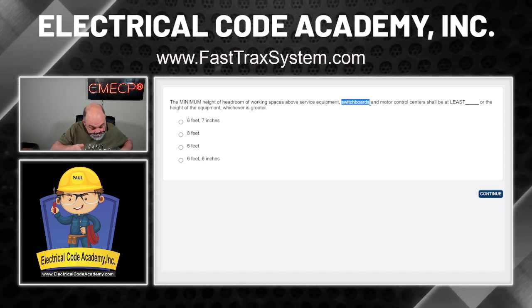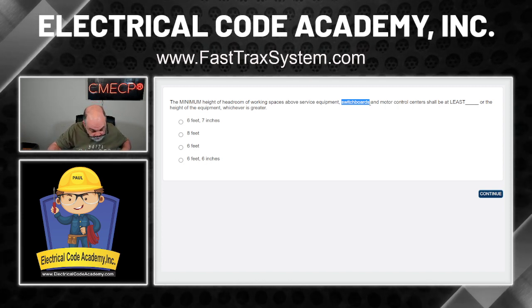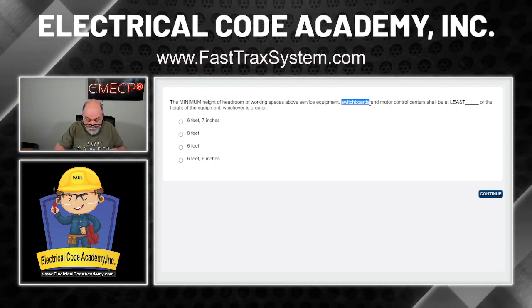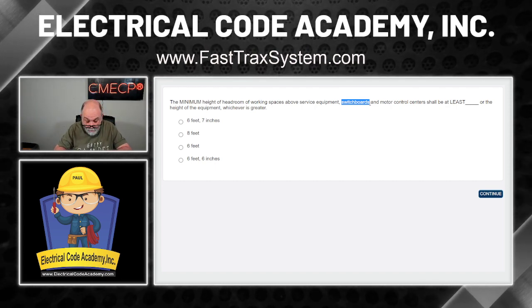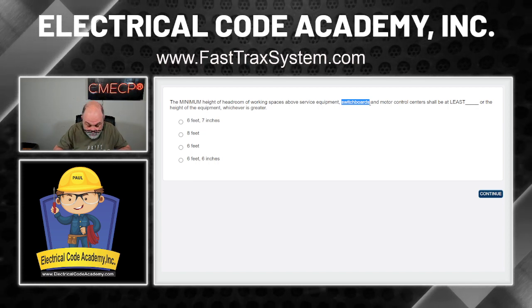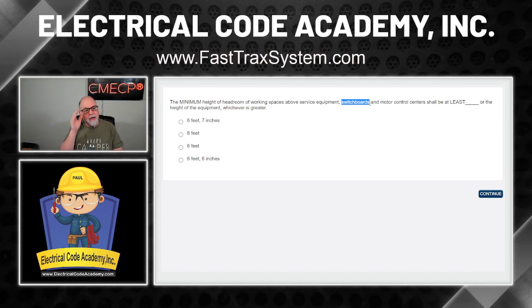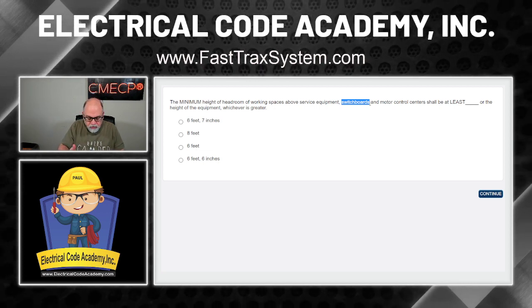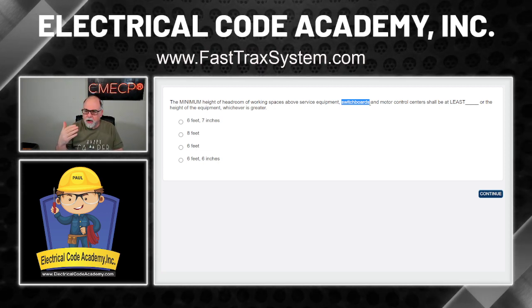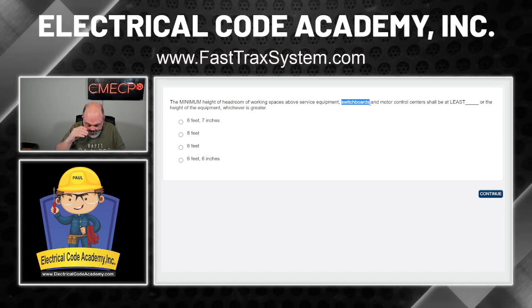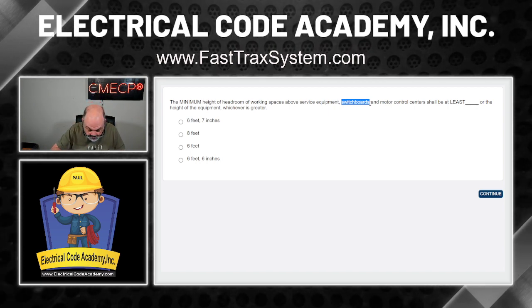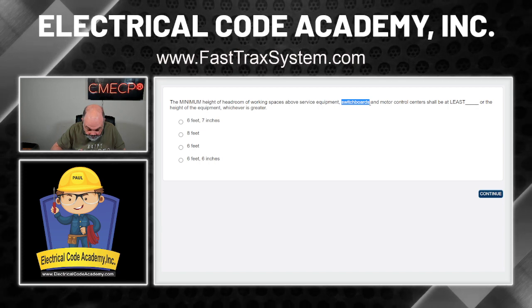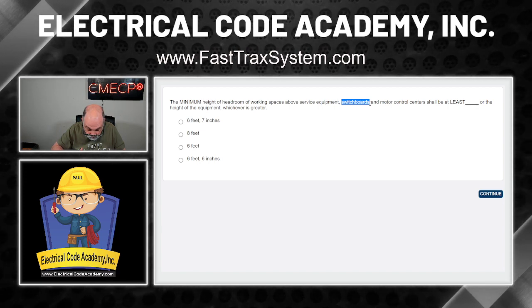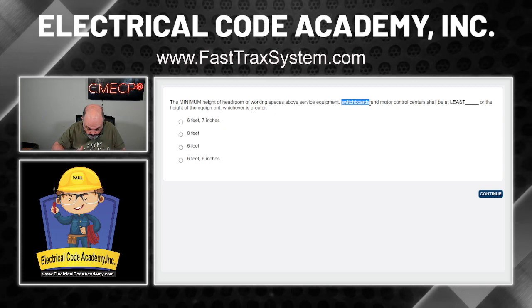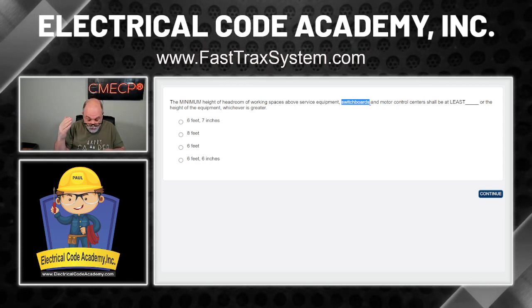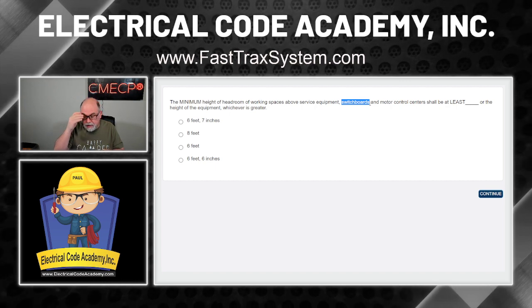You should be doing it with me. So I'm going to look in here and see if I see, okay, I see switchboard. And then underneath, I see clearances. And it's 110.26 again. Okay. Now, as you get better, you're going to notice that the other references like 408, that's just the article for panelboards, switchboards, and switchgear. So you'll understand that. And so you'll see that, and you go down, and I'm just looking down. Locations. Okay. Working spaces. Right at the bottom of switchboards, it says working spaces 110.26.